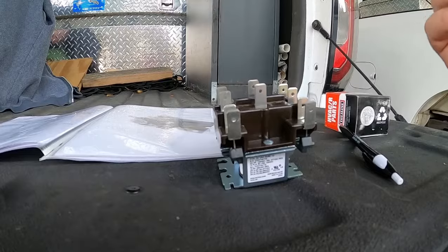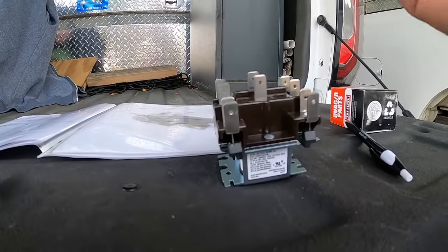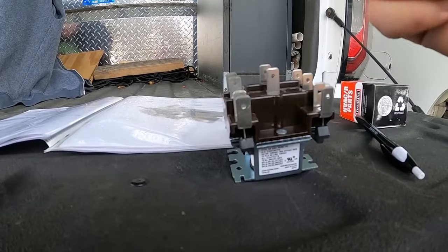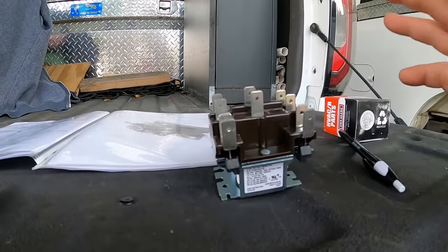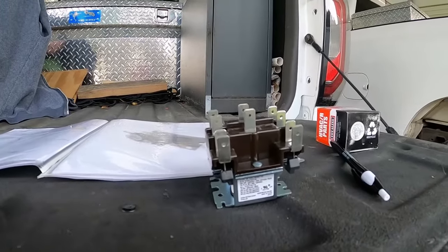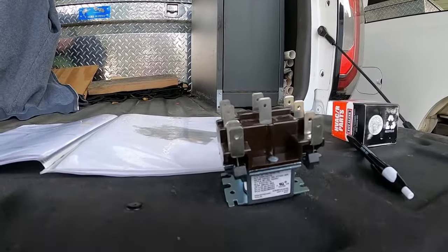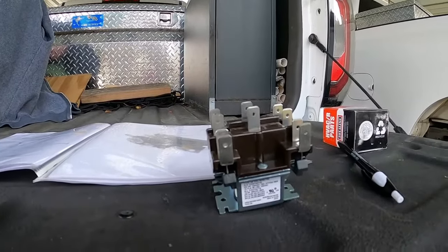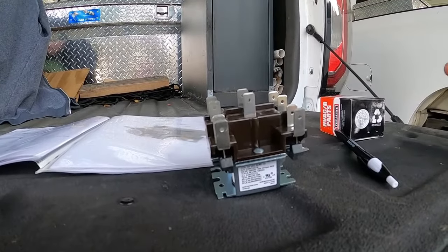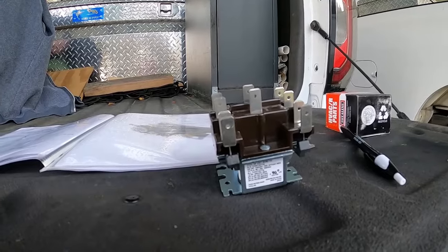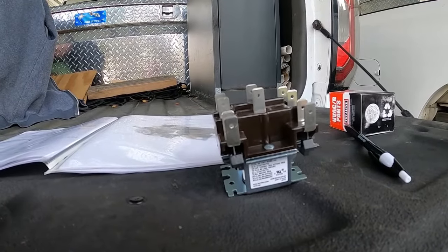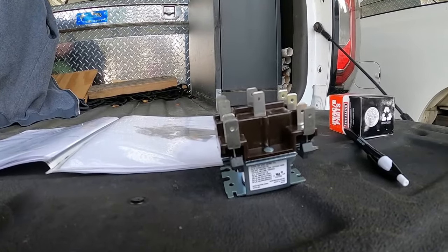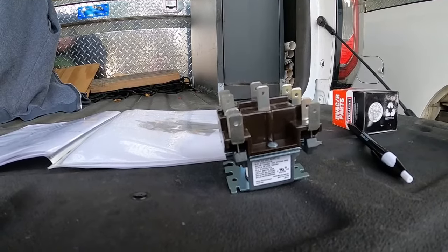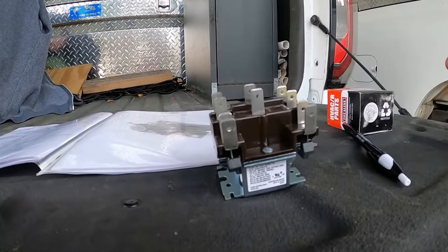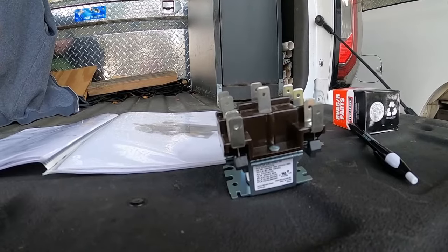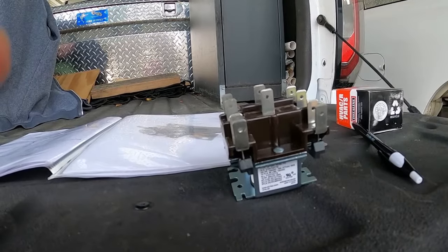And then I've got sequencers, relays, contactor, thermostat, transformer, and I basically just pull all the wires off of it, and you've got your controls, you've got your loads, and I have them wire that thing up and then cycle the thermostat through its operations, and make sure everything comes on when it's supposed to be on, everything's off when it's supposed to be off. No blown fuses, things like that. Nothing's cross-wired. Everything's hooked up with circuit breakers and protectors, things like that.